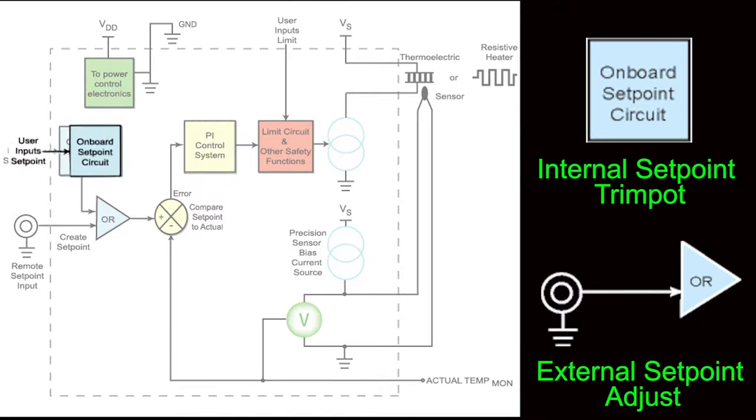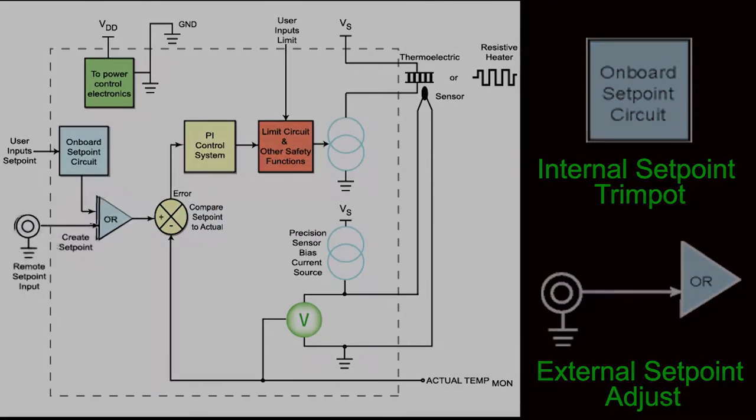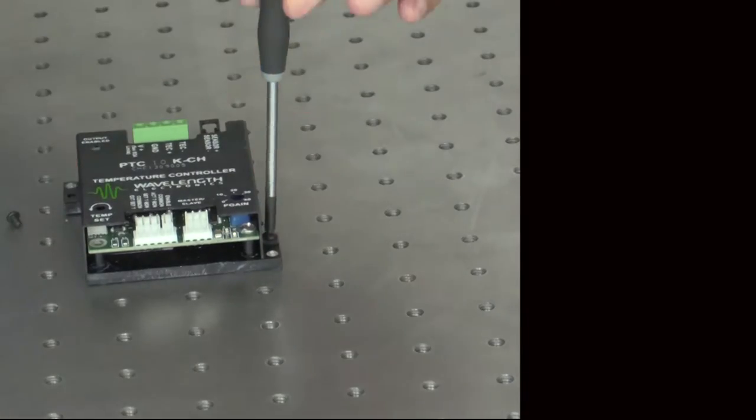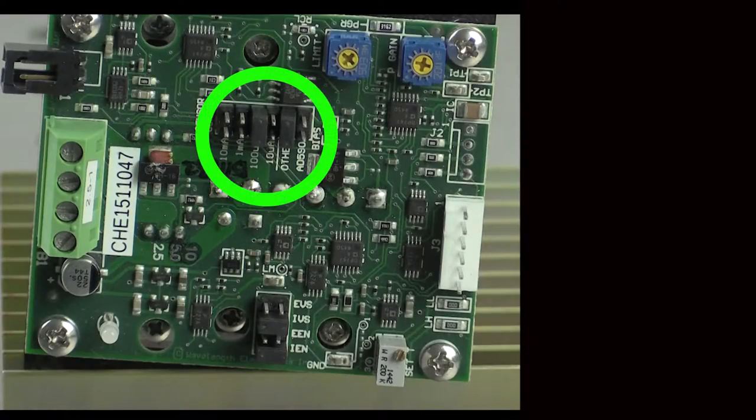The setpoint voltage can be generated by the PTC using the onboard potentiometer or by a remote voltage. Before wiring up the PTC, two internal jumpers need to be set properly. Remove the cover, two corner screws, and locate the jumpers. One set is for sensor and bias current selection.